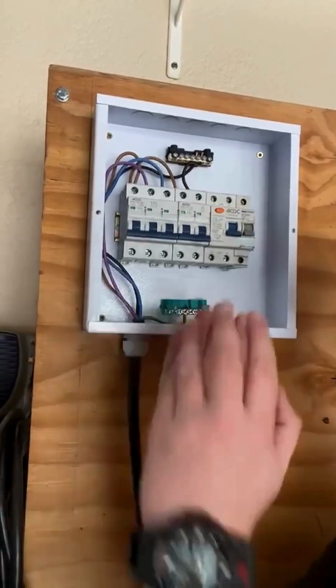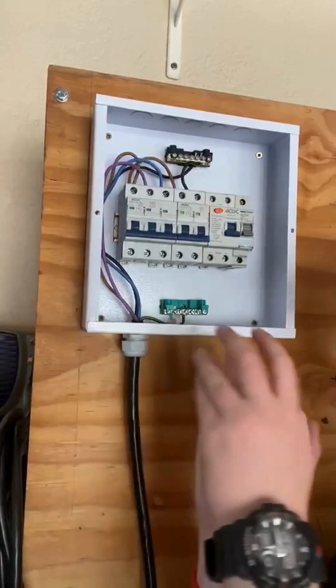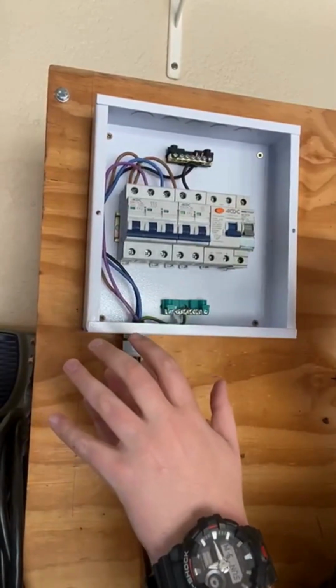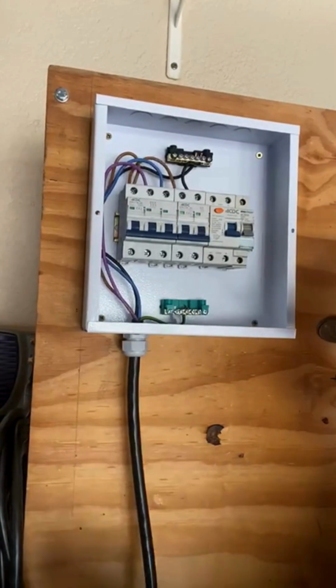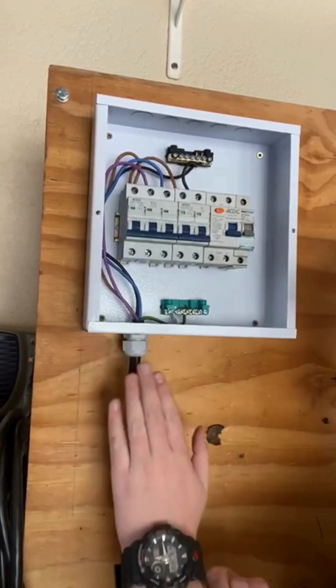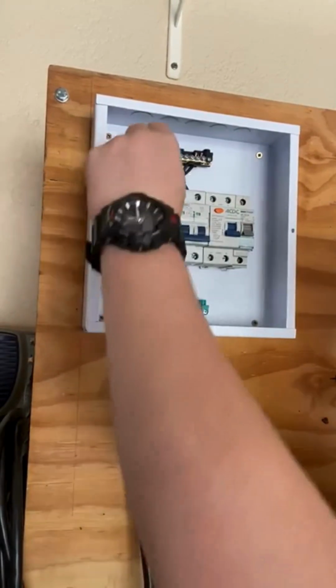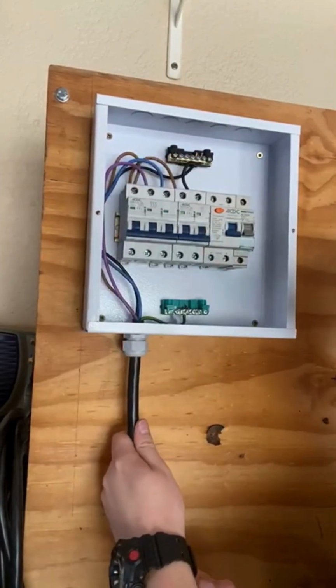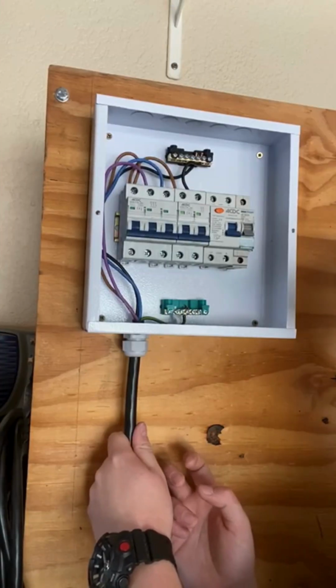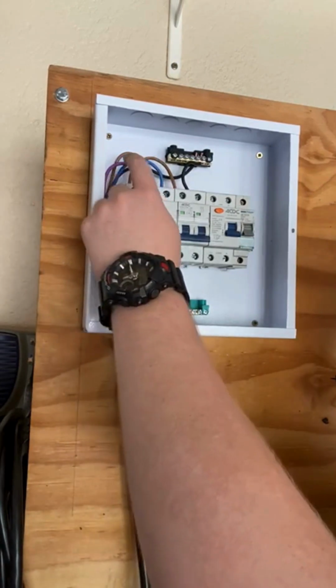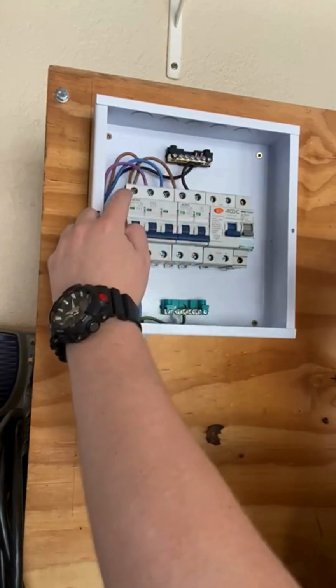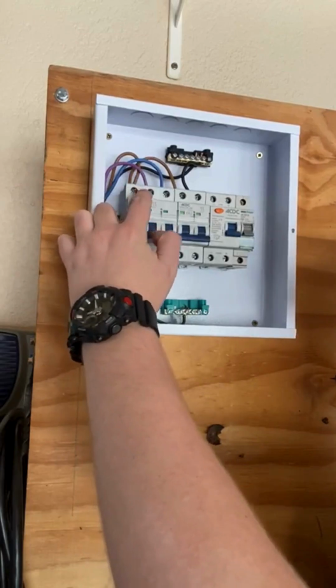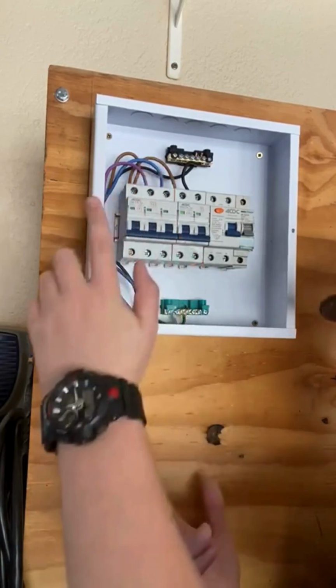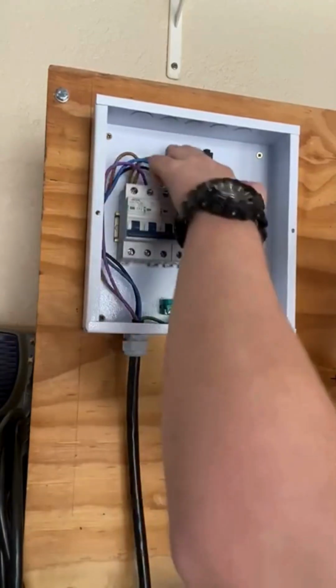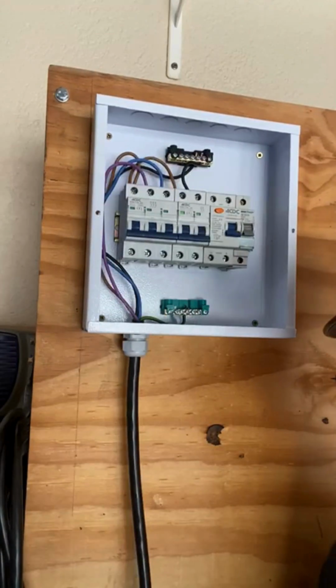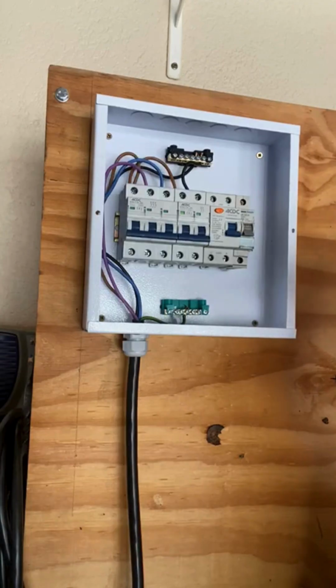Like I said earlier, this panel is supplied by three-phase electricity. We've got our cable here coming in through the DB and into the three phases. This is a three-phase cable, where each live phase is connected to L1, 2, and 3 - so you've got live 1 on L1, live 2 on L2, live 3 on L3. Then obviously you've got your neutral connected to the neutral bus bar, or the neutral bar.